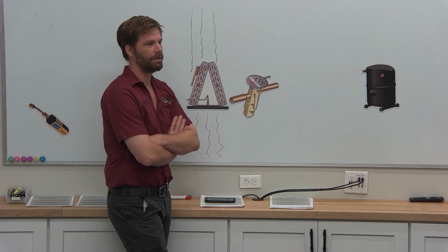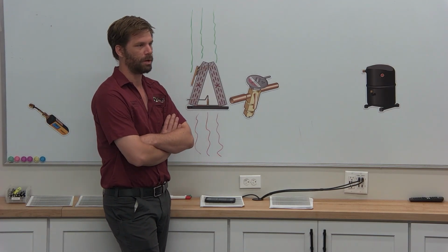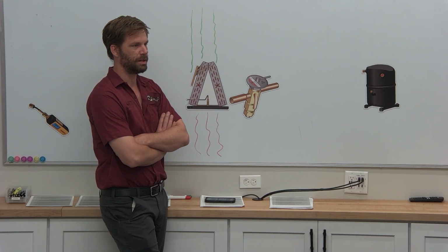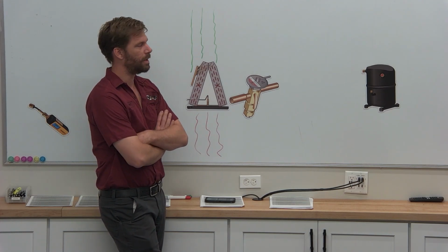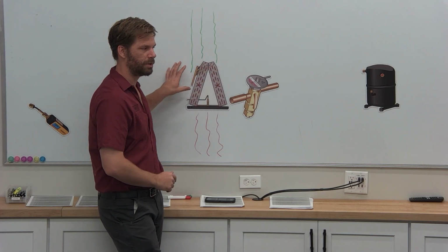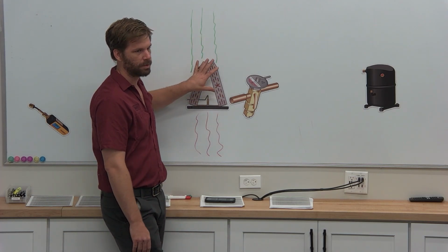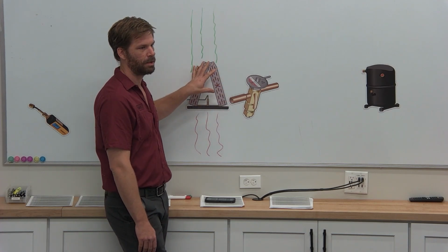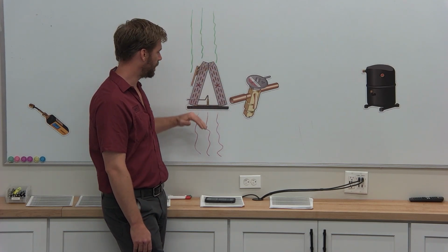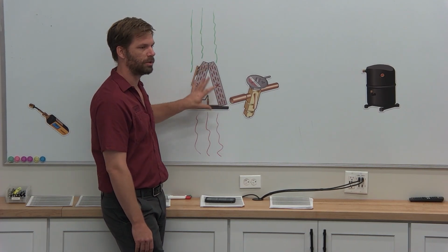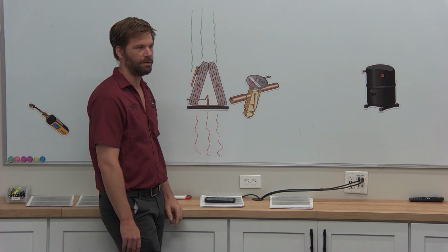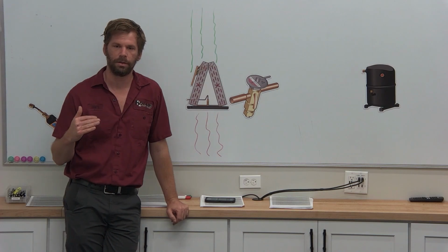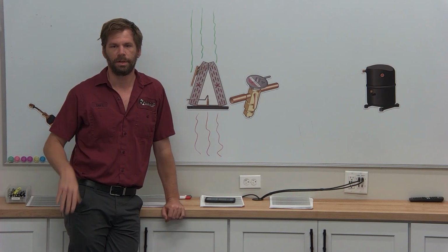It looks like everything's where it should be, except for we have this really low split, which is giving us a clue that the ratio of refrigerant to air is off. Our pressures tell us we have enough refrigerant, but our temperature split tells us we have a lot more load on this coil than what it's designed for. So we can bring back this temperature split, this blower speed, bring it down.